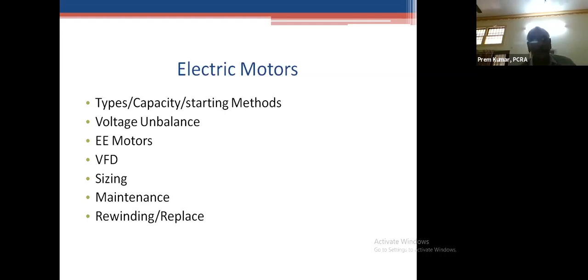See what happens is the equipment supplier already gives an allowance of 10%, and over and above this, there is the standardization. For example, we don't have a motor for 6 HP. We necessarily go for 7.5 HP. And this 7.5 HP itself, we were going to oversize it. Then you can imagine the oversizing. If you see the curve, there is a loss of efficiency, loss due to no-load losses, unnecessary wastage of energy.